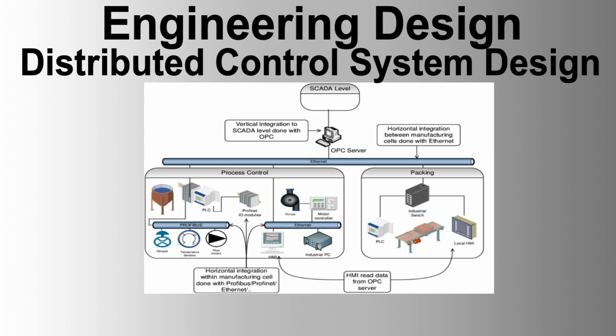7. Testing and validation documentation. Test plans and procedures for factory acceptance testing (FAT) and site acceptance testing (SAT) must be provided. Test reports documenting the results of all testing activities, including performance tests, integration tests, and validation tests, must be included. Procedures for verifying system functionality, performance, and compliance with specifications must be detailed.